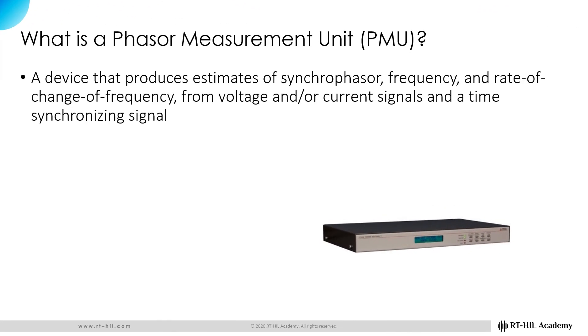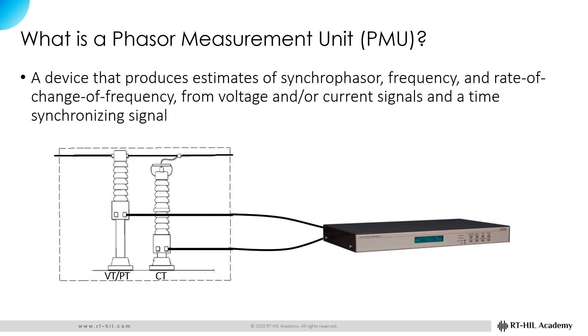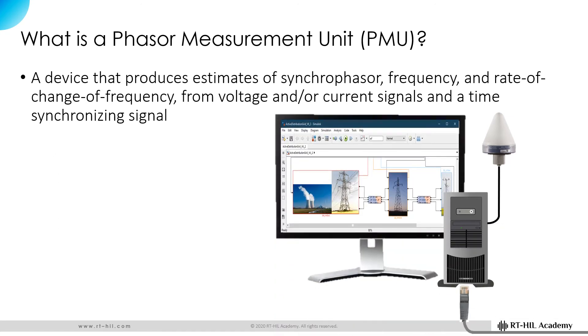A PMU is a device that produces estimates of synchrophasor, frequency, and rate of change of frequency from voltage and current signals and a time synchronizing signal. The estimated quantities are time-stamped using the precise time provided by GPS signals, and then streamed into communication networks. The PMU functionality is embedded in most real-time simulators, so they can be configured to compute synchrophasors out of simulated voltage and current waveforms, time-stamp them, and stream them into communication networks. Now it is time to have a closer look at the IEEE C37.118.2 communication protocol.